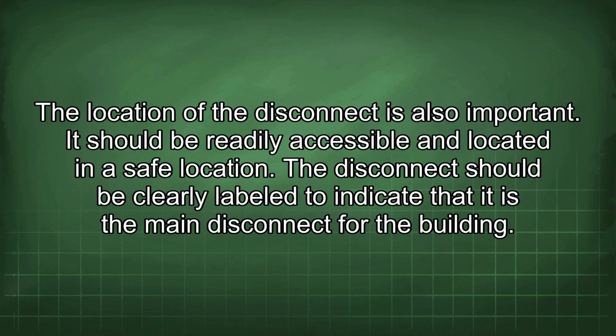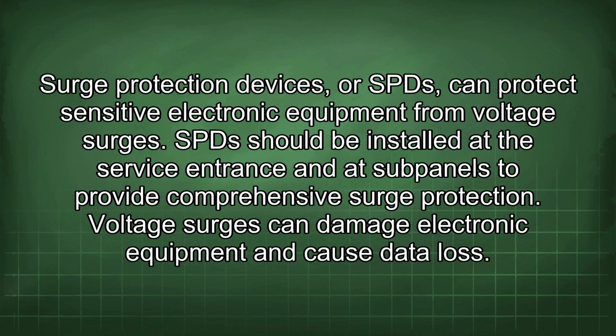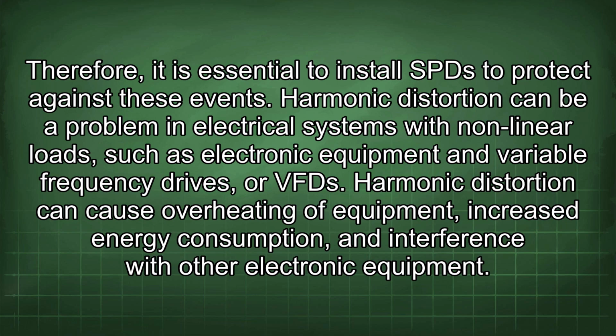The location of the disconnect is also important. It should be readily accessible and located in a safe location. The disconnect should be clearly labeled to indicate that it is the main disconnect for the building. Surge protection devices, or SPDs, can protect sensitive electronic equipment from voltage surges. SPD should be installed at the service entrance and at subpanels to provide comprehensive surge protection. Voltage surges can damage electronic equipment and cause data loss. Therefore, it is essential to install SPD to protect against these events.